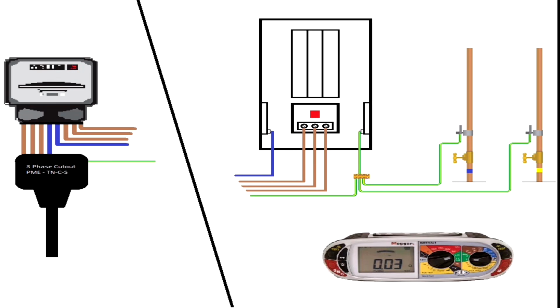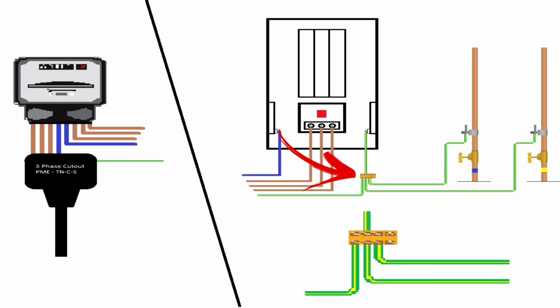Exactly the same rules apply: turn off the supply, notify people, and all the other stuff that we have to do, but it's removing those parallel earth paths I want to concentrate on in this video. So what we've got now is we've zoomed in to the MET, the main earthing terminal, and you can see there the bottom conductor coming in from the left-hand side brings the earth in from the supply source, and a single earthing conductor then into the distribution board, and our bonding conductors are on the right-hand side, in this case going off to gas and water that are metallic incoming, therefore offering a parallel earth path because they'll be connected to the greater mass of earth being a metallic water pipe and a metallic gas pipe.